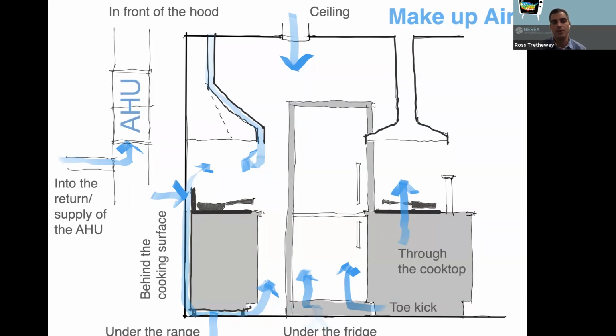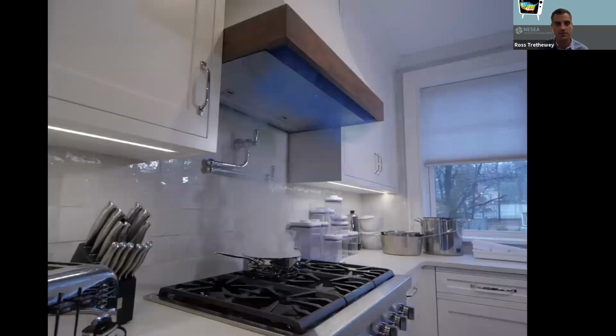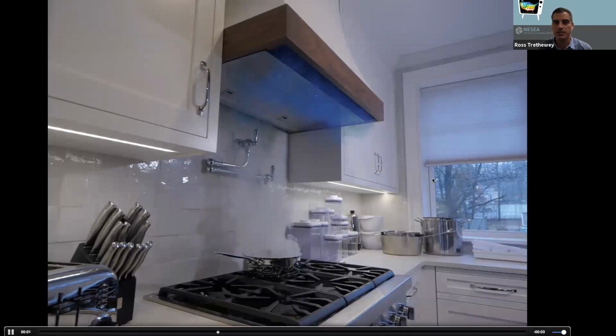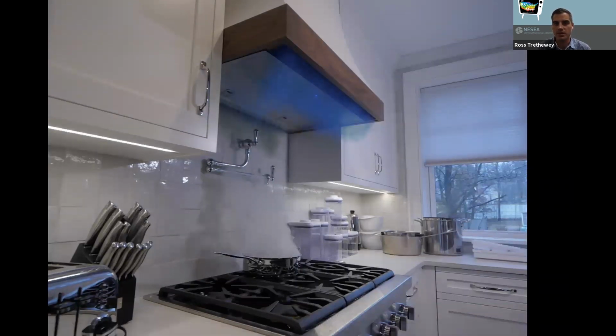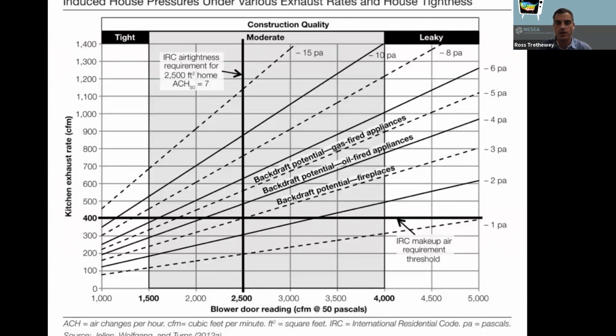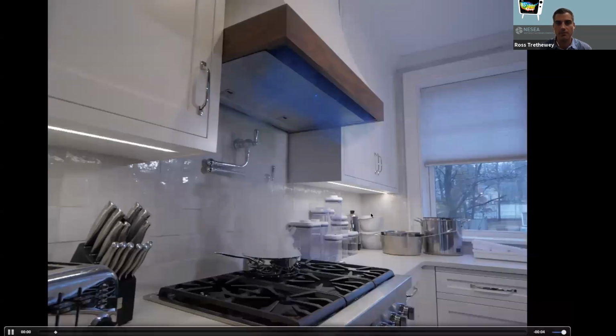So there's also aesthetic challenges. How do you bring the air up behind the cooking surface? Just to give you a highlight on some different ways, and we'll get into more of this in the conversation, here's one way that we did it on a recent project. This is called the hood within the hood concept. Outside air is coming in, the blue, and exhaust is leaving up through the backside of it. And you can see we're getting no spillage. We're getting proper capture of all the smoke off the cooking surface, and that's most important.